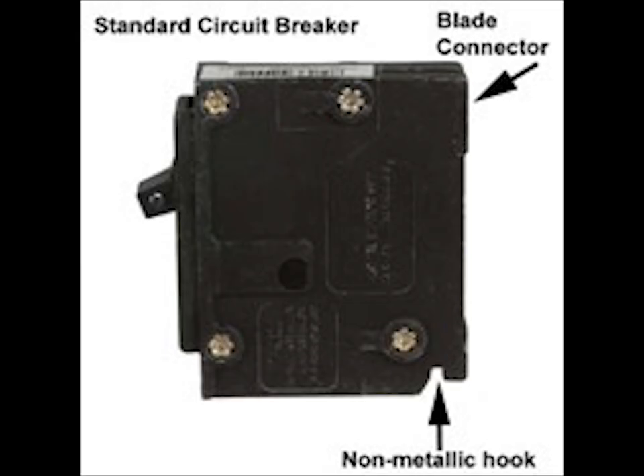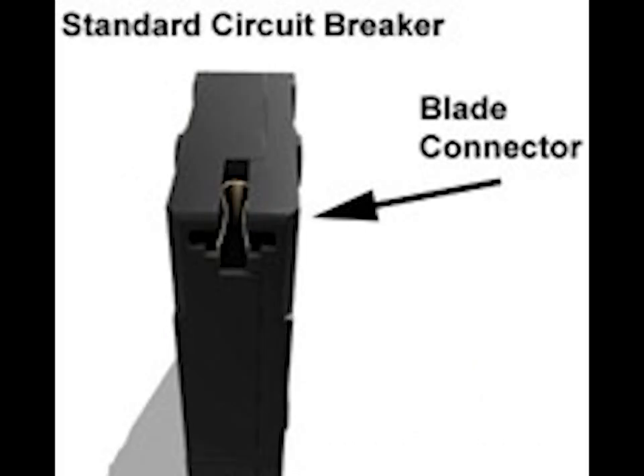Circuit breaker types. Normal, not plug-on neutral. The circuit breaker hooks into the load center with a non-metallic, non-conducting hook. The circuit breaker has only one metal connector on its back. This blade connector is for the power connection. This circuit breaker has only one screw to attach a wire to the breaker. This is for the black wire to your outlets, lights, etc.